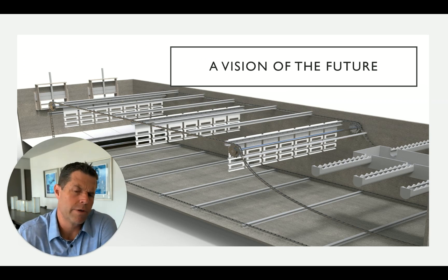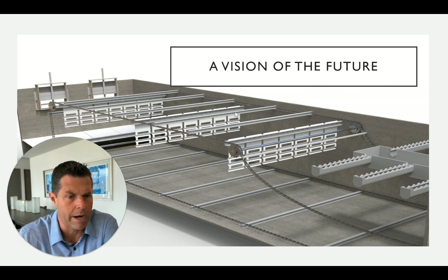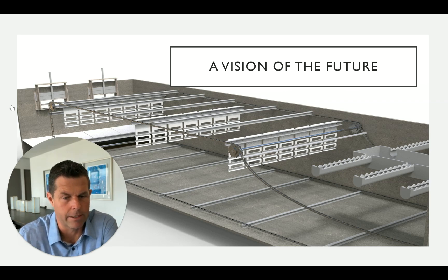This is the other reason that rectangular basins make great candidates for optimization. Because we're able to correct flows at multiple locations across the axis of the tank, we can introduce a secondary set of baffling and a third set of baffling to really make the most out of the existing concrete that's available to us in a rectangular basin.